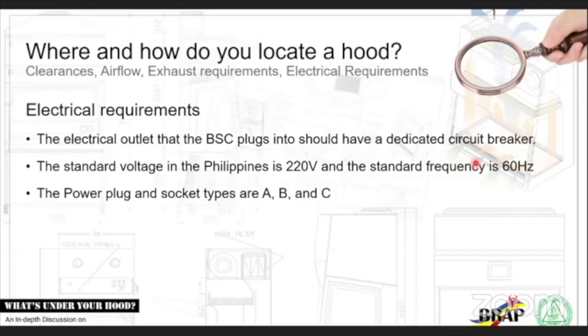Pag bumili kayo ng biosafety cabinet, don't forget to look at their power requirements. Okay. And there should be a dedicated circuit breaker for your biosafety cabinet. Or in case here in the Philippines, I think Luby mentioned this, you need to have a UPS long enough to give you enough time to close your system if anything goes wrong. Now, the power plug in the Philippines, socket types are A, B, and C. If you're planning to get your biosafety cabinet all the way from Australia, you might have a problem because they have a totally different power plug. So you need to check your power plugs, okay?